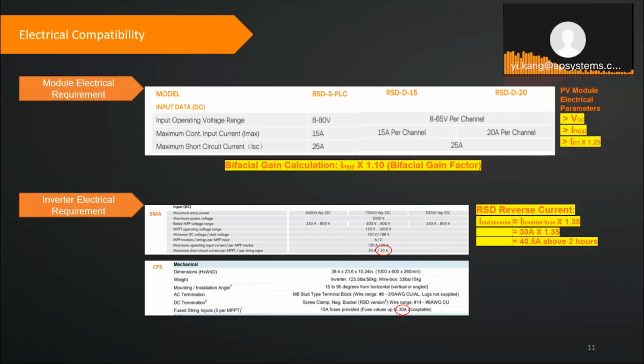Thank you. The rating for the RSD-S-PLC, the single, is 15 amp. You can tell from here, the device, we have a 15 amp and a 20 amp, but that's mainly for the commercial jobs. They want to go to higher current products with bifacial, much higher current on this side. But normally in the residential market, they still go within the 15 amp right now.